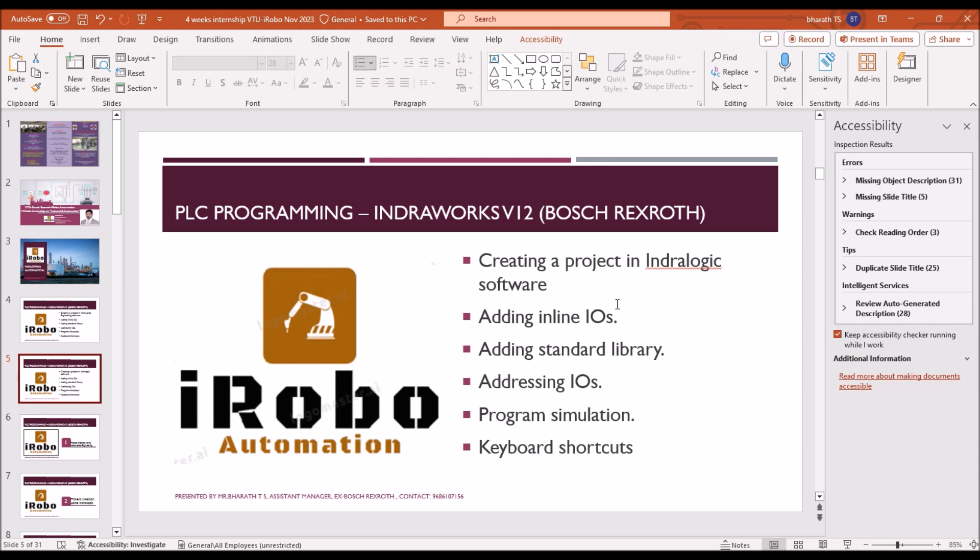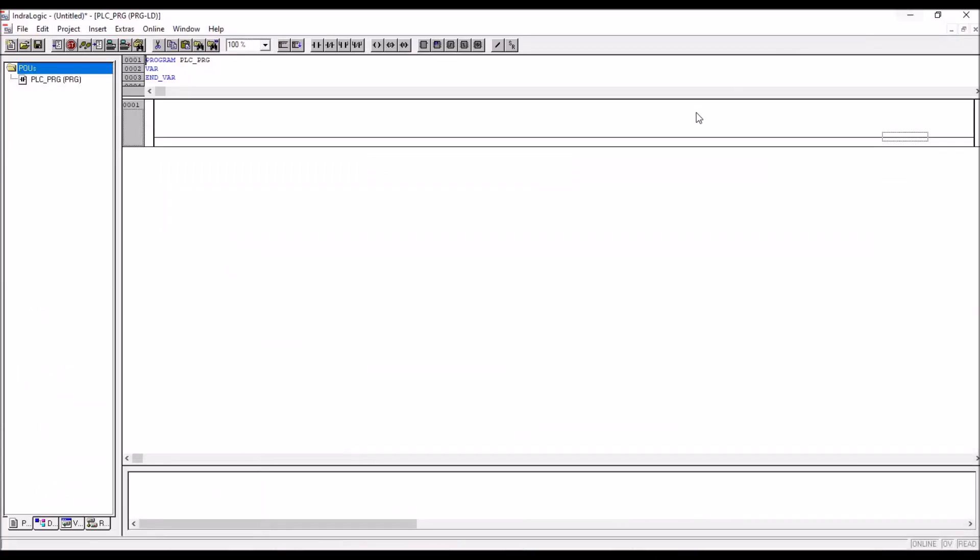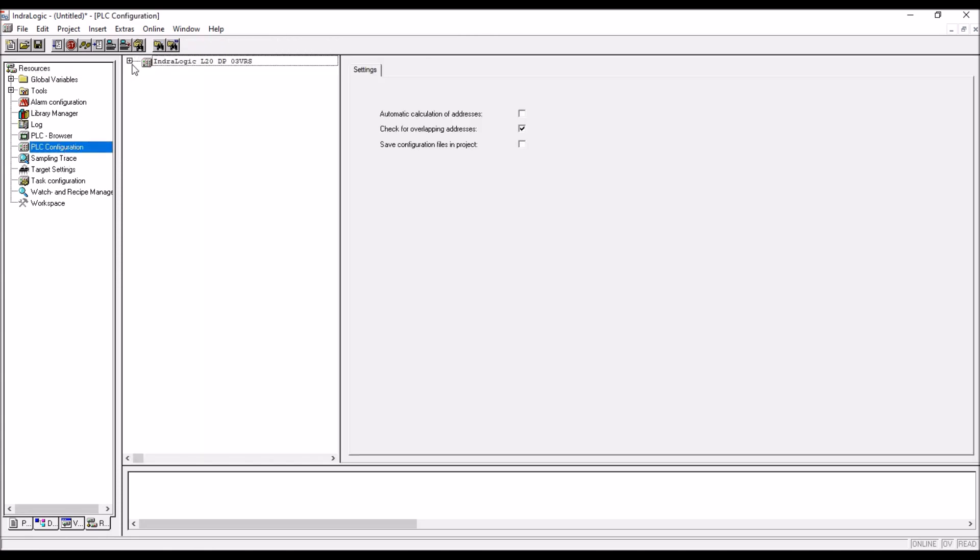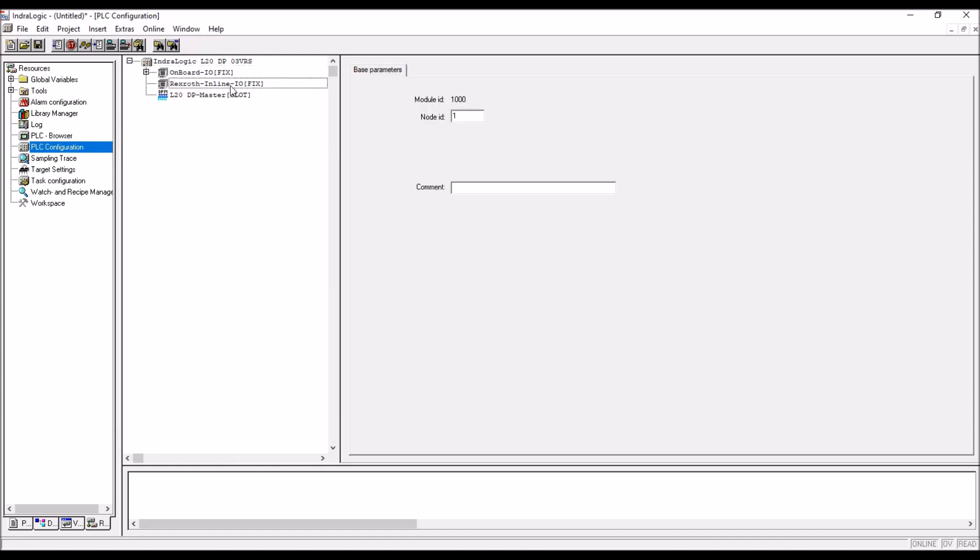Inline modules you have to add, otherwise you will get error. Go to the resources tab, that means in the bottom left corner there are four tabs. Go to resources. There PLC, go to the PLC configuration, click on the placeholder, IndraLogic. There inline, you can see that inline is empty.